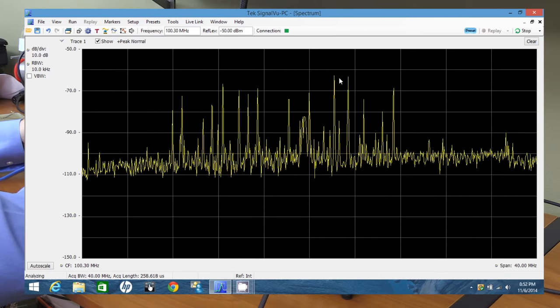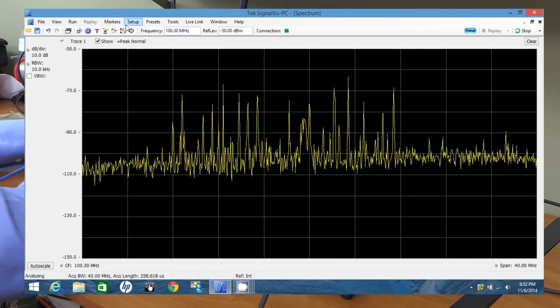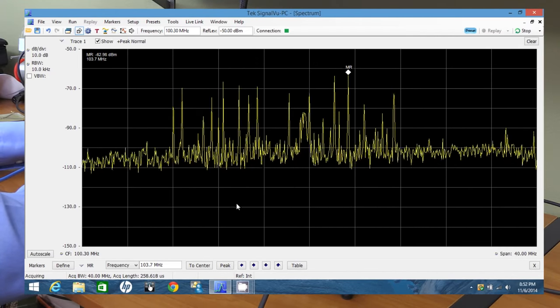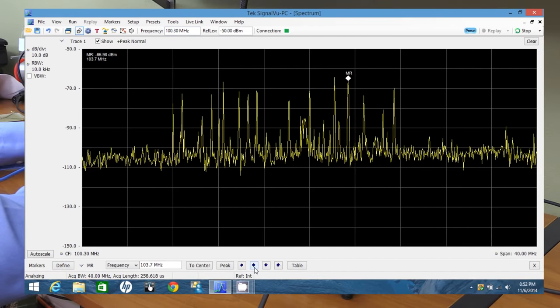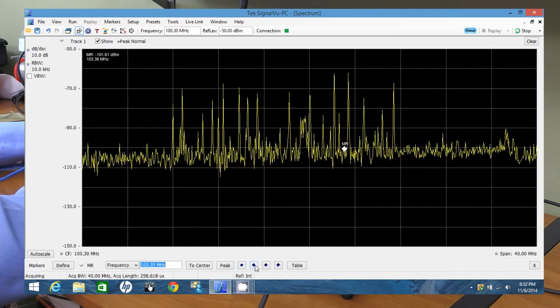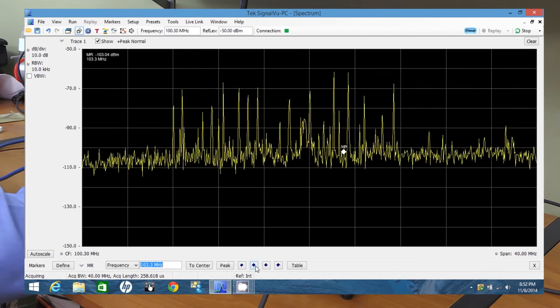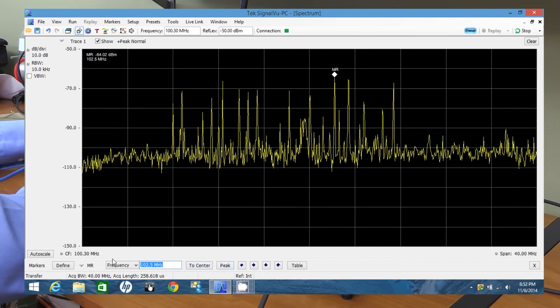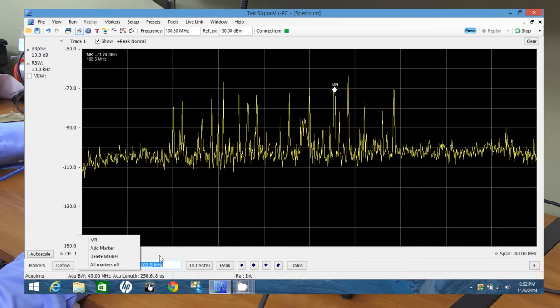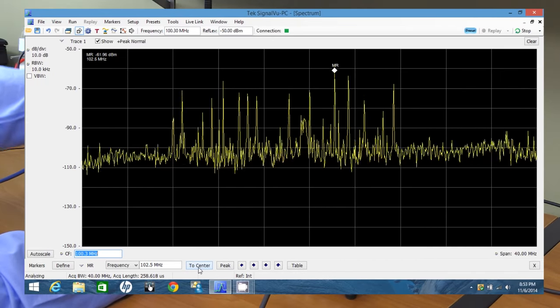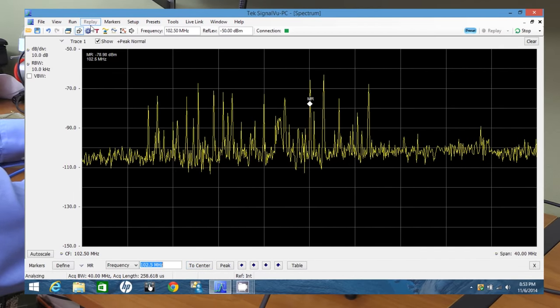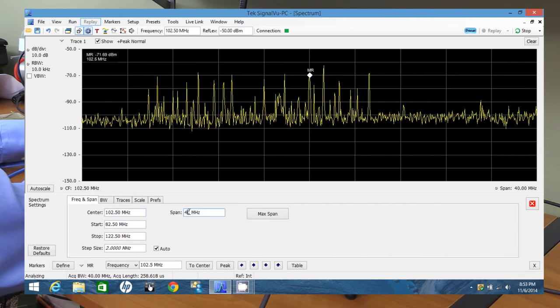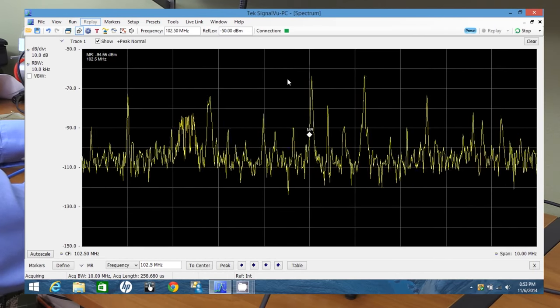Here we go. Here we see all the peaks. Maybe let's take a different one because that one looks kind of crowded there. Let's do markers, peak. That one looks kind of good. That's the highest peak. Just in case you missed it early, all you do is markers, hit peak, and you can click to the right, getting the next peak over into that direction. Or you can hit left, get the next marker, next peak into that direction. It's really straightforward. It's really easy to figure out. You can actually add more markers. Just click here, click on add marker, and you can add a bunch of markers on your screen here, no problem. And you can also center your spectrum around this marker. Just hit to center. All of a sudden, we've got our radio station in the middle. Now we can reduce our span, which is at 40 megahertz. Let's just reduce it to 10. There we go. We've got a radio station jumping around in the middle.